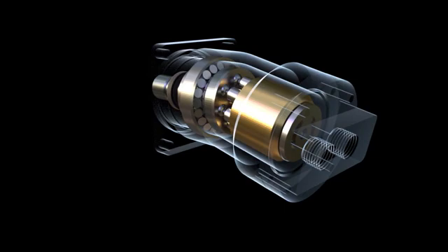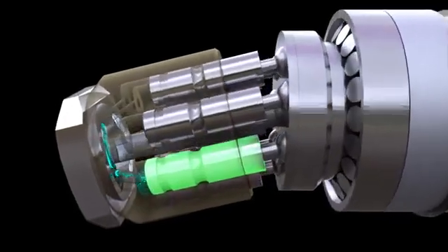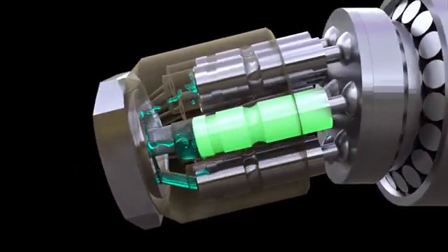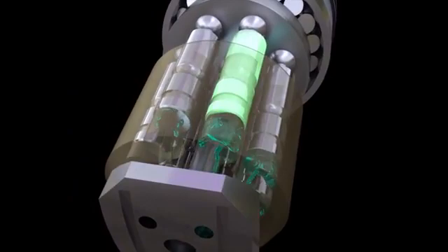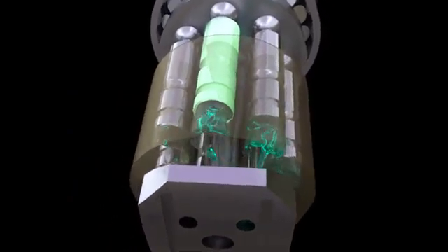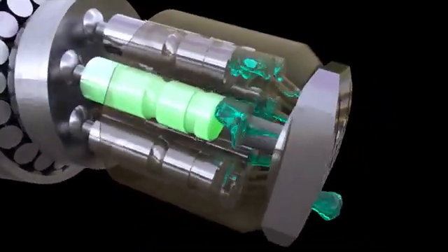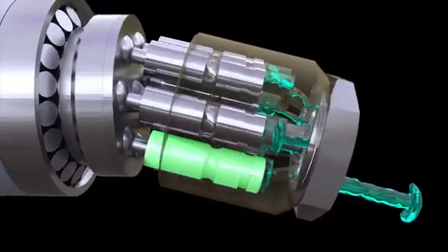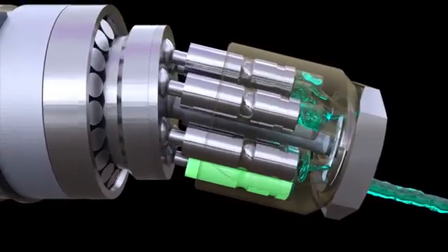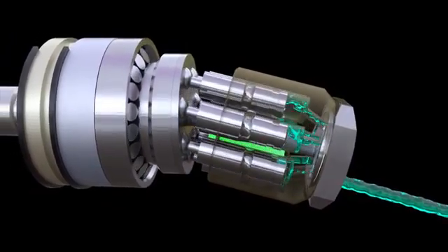The fluid from the tank is supplied to the inlet channel of the pump, from where it is sucked by the pistons. Consider the operating principle of one of the pistons. When moving through the suction area, the piston moves and increases the volume of the working chamber. Due to the increase in the volume of the chamber, the pressure in it drops and the fluid fills the chamber under atmospheric pressure. Having reached the extreme position, the piston begins to move in the opposite direction, thus reducing the volume of the working chamber, and the fluid is displaced into the pressure channel. Having reached the second extreme position, the piston begins to increase the volume of the chamber again. The suction begins, and the cycle repeats.